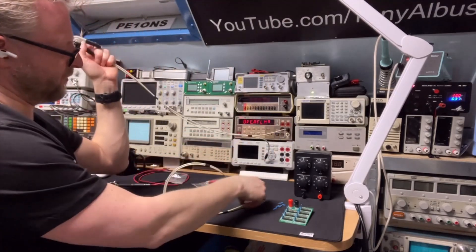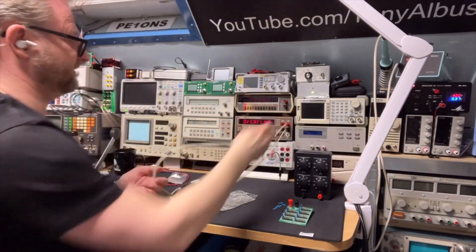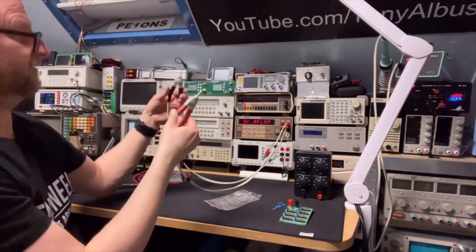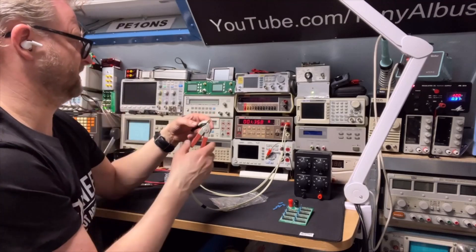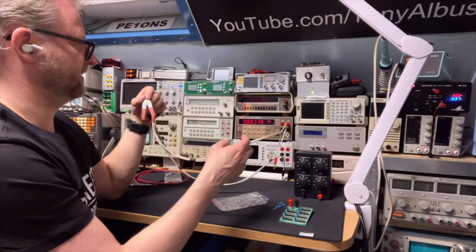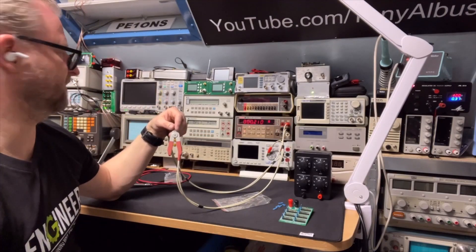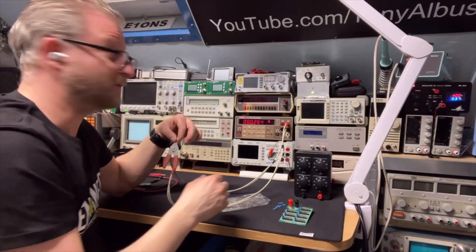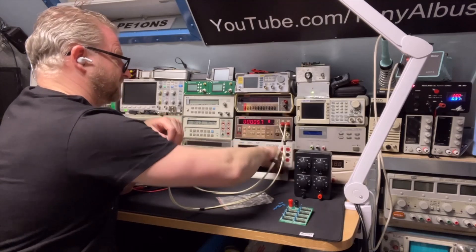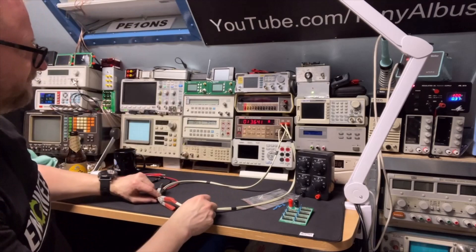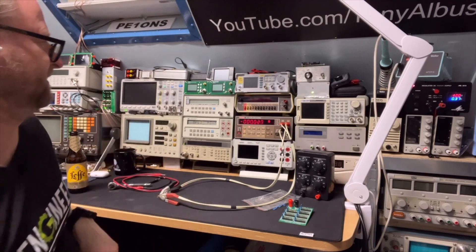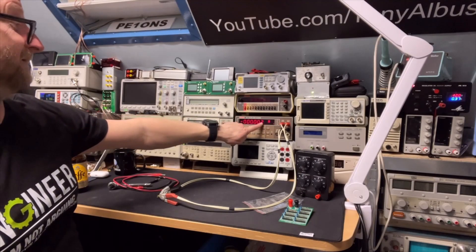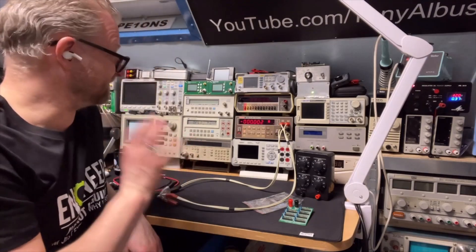It just compensates for the loss in the cable. I will only do first one of each and then we should have the same because then we use the two wire system. As you can see we have now 0.2 ohms, so the cables are a little bit better than these Chinese cables. But what will happen if we use the four wire system. So now we're gonna compensate the loss of the cable. Look. 0.003 ohms. So that's what the four wire system does. It really compensates out.